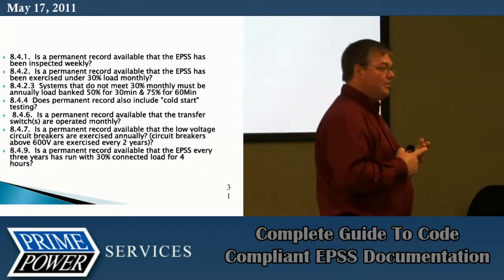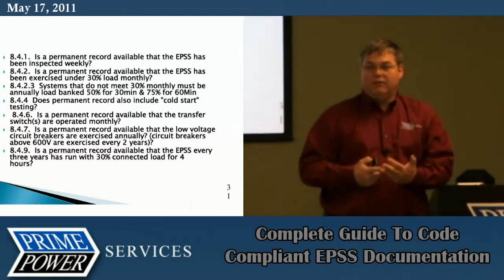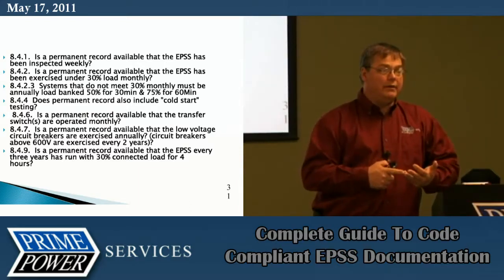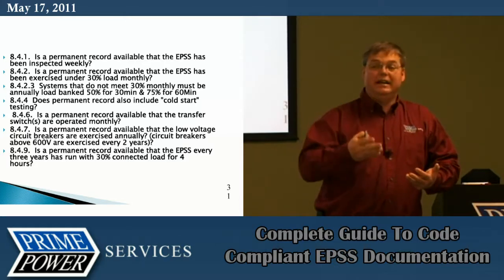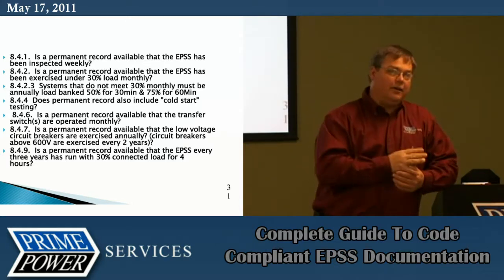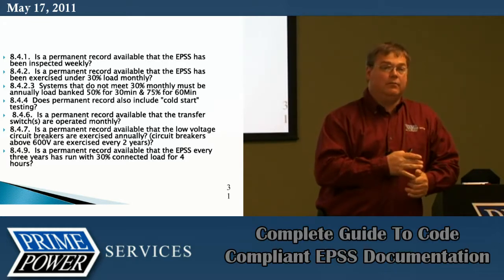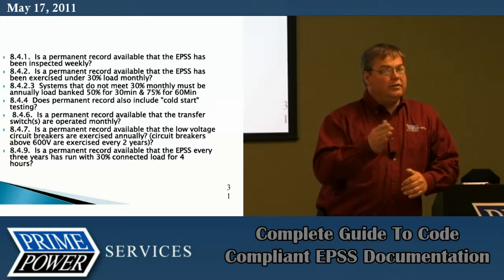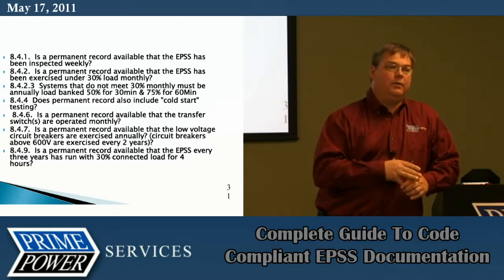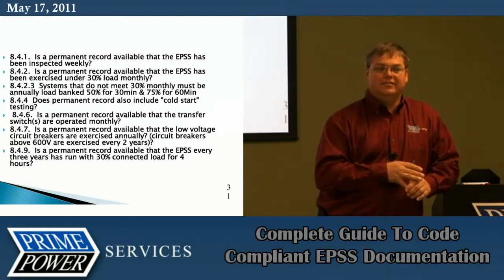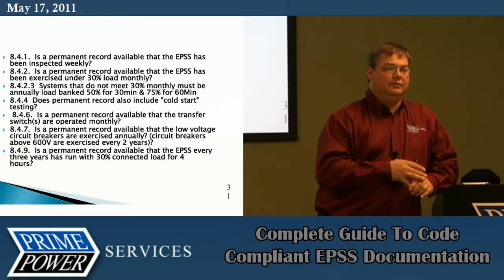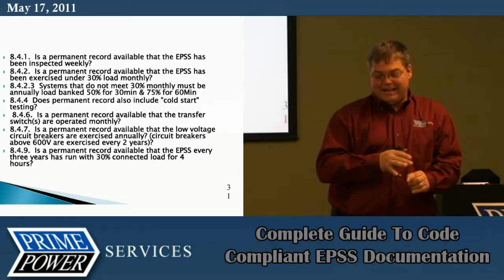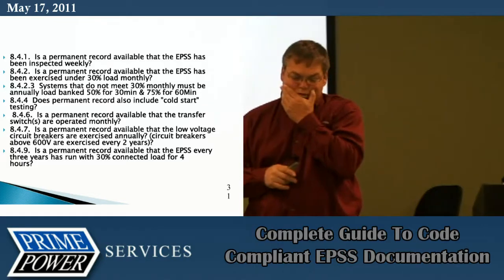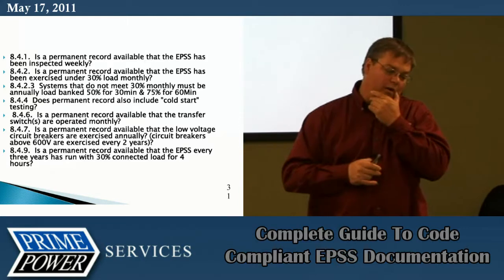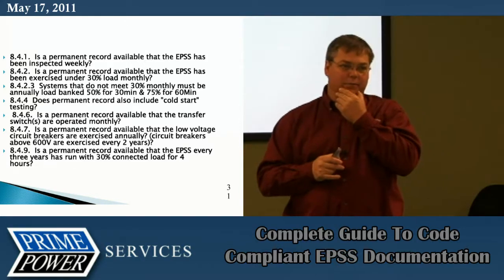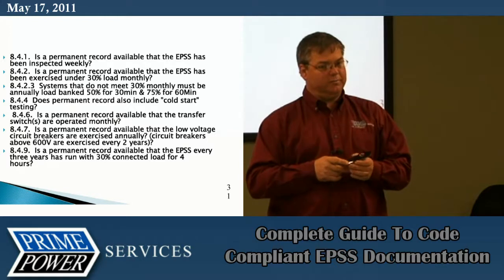You can have on it the time it started and the time it stopped. You can have on it what the hour meter reading was at the beginning and what the hour meter reading was at the end. And I have personally found people that had hour meter marks that changed from run to run. You know, a little pencil whipping going on. The inspectors that are out there have got enough sense to look at that time stamp. One of my favorite questions to ask when I'm doing that survey is, okay, you have 312.2 and then you have 312.8. What's the 0.2 and the 0.8?